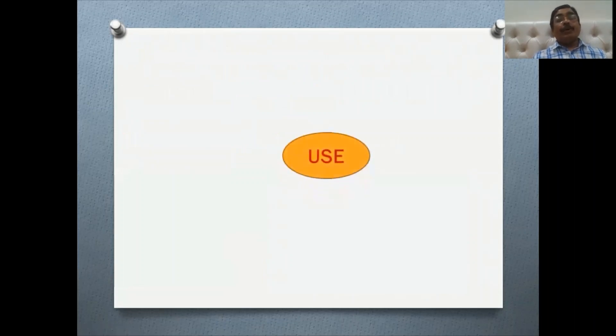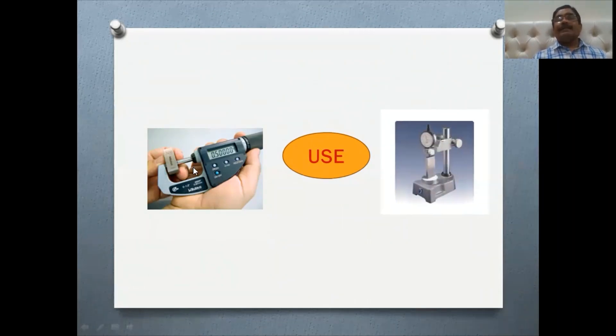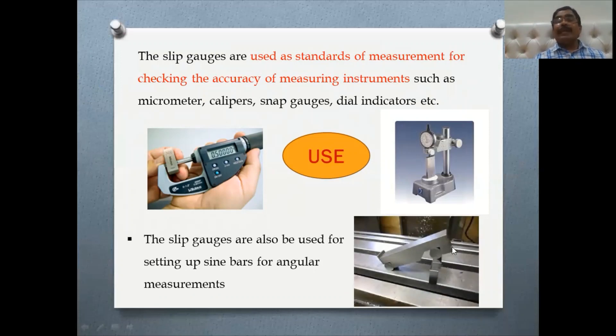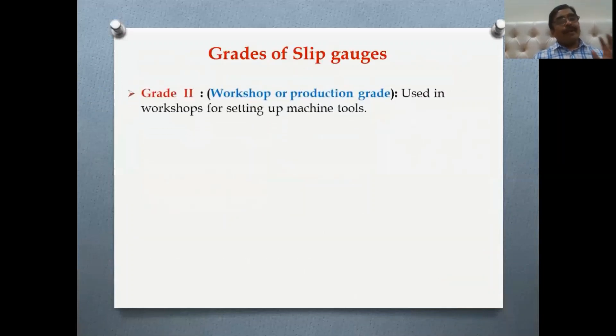The uses of slip gauges: first, they act as a masterpiece because they are highly accurate. Here I'm checking the accuracy of a micrometer with the help of a slip gauge. Second, we are setting a dial gauge using slip gauges. We can also use them with a vernier, and slip gauges are also used to set a sine bar — the instrument used for measuring angles.